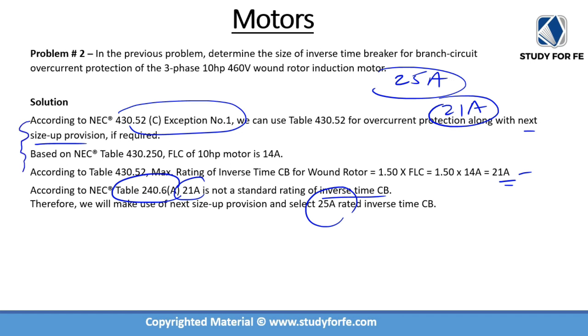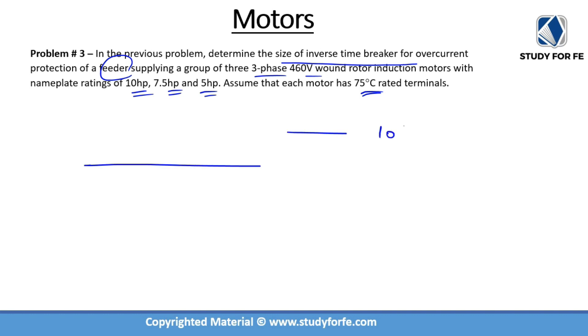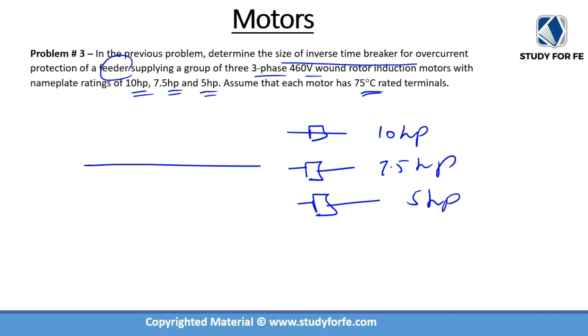You can see that we are now making use of different code sections, some within the same article and some in other articles. Problem number 3 further builds upon the previous two problems and asks us to calculate the size of an inverse time circuit breaker for overcurrent protection of the feeder supplying the group of three-phase 460V wound rotor induction motors. The difference here is that problem 2 sized the OCPD for the 10 horsepower branch circuit, whereas problem 3 is sizing the OCPD for the feeder.